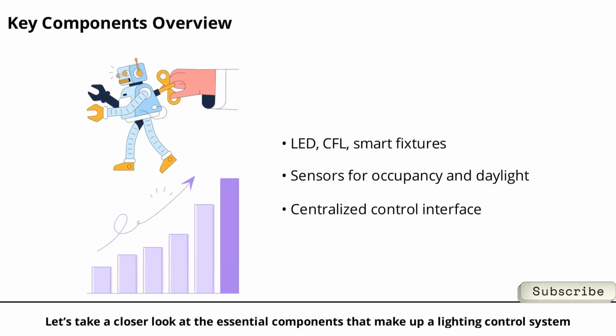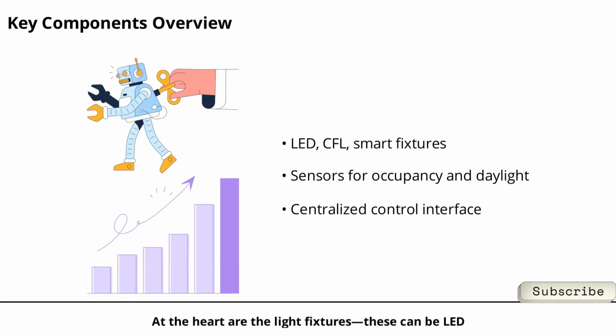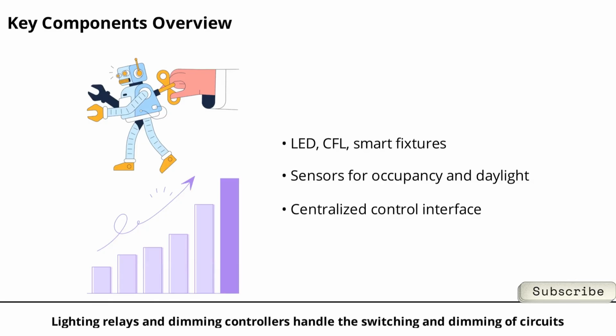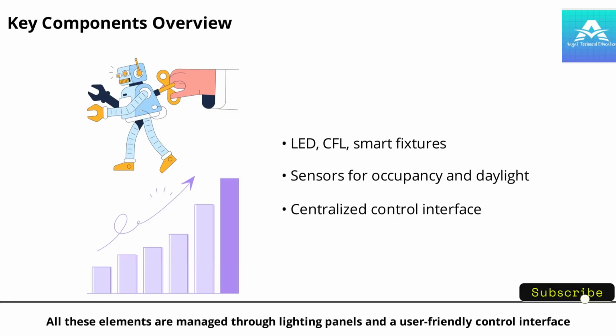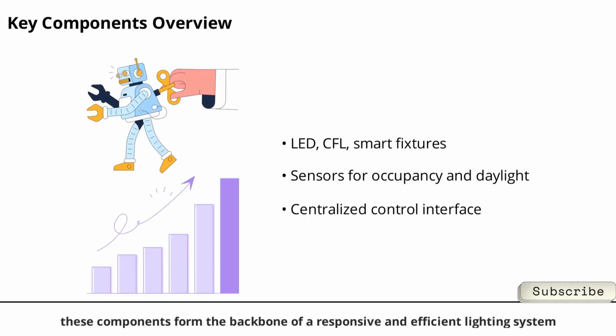At the heart are the light fixtures. These can be LED, CFL, fluorescent, or smart fixtures. Switches and dimmers, whether manual or digital, allow for basic control. Occupancy sensors detect human presence, while daylight sensors measure natural light to adjust artificial lighting. Lighting relays and dimming controllers handle the switching and dimming of circuits. All these elements are managed through lighting panels and a user-friendly control interface, often integrated into the BMS. Together, these components form the backbone of a responsive and efficient lighting system.